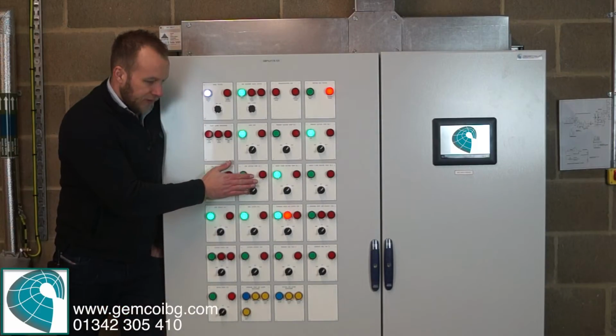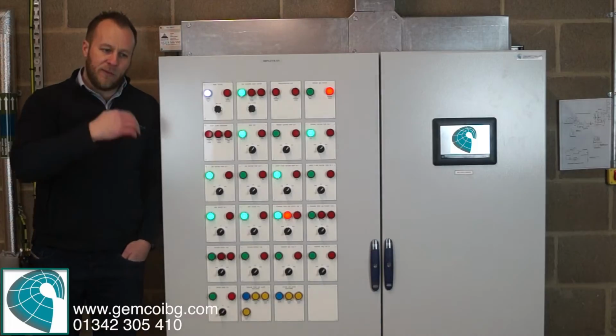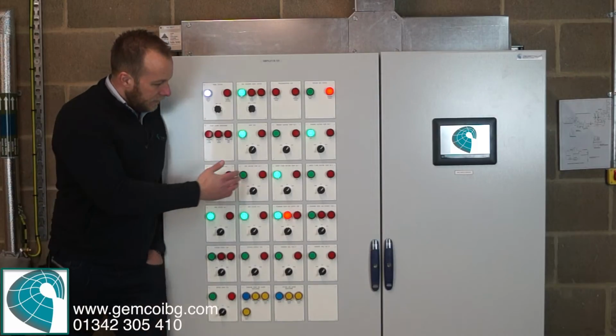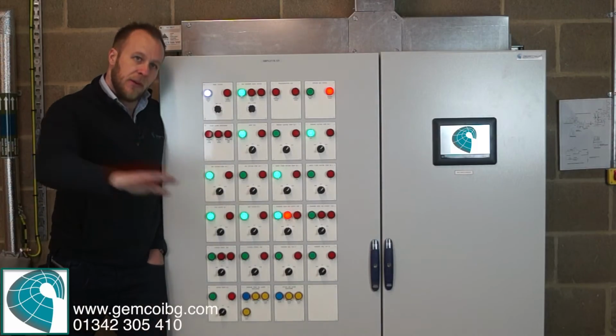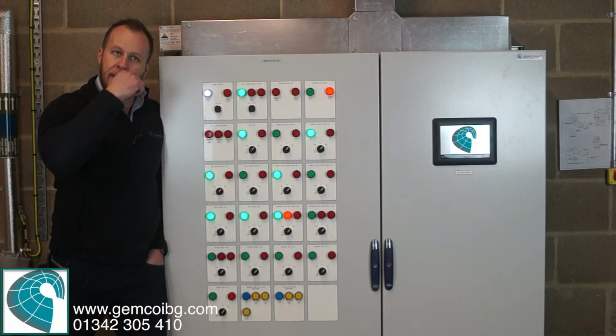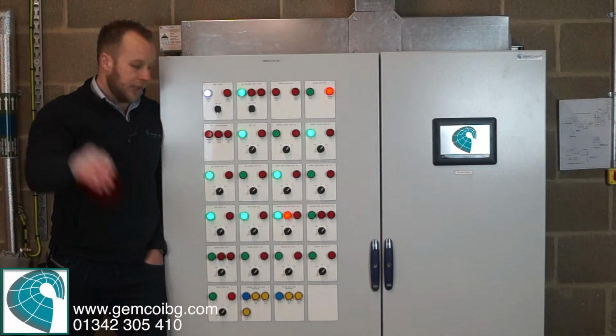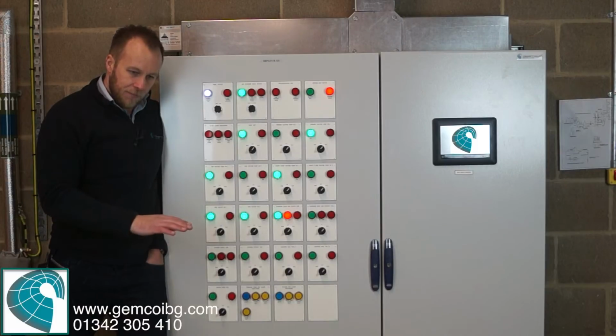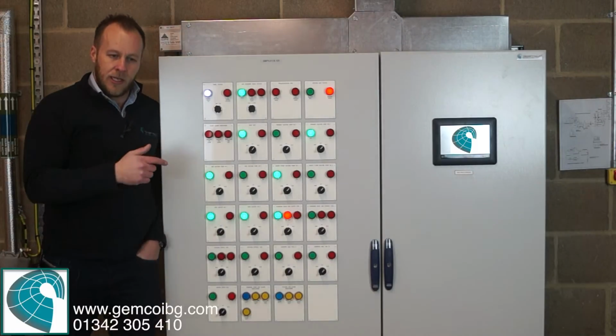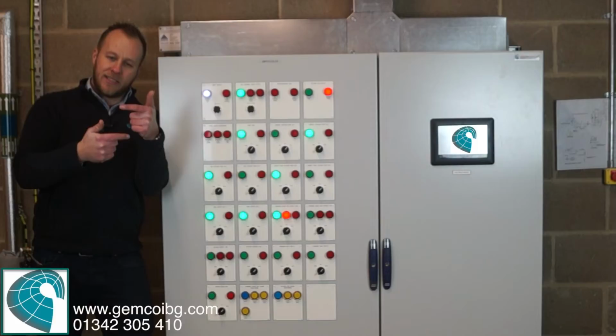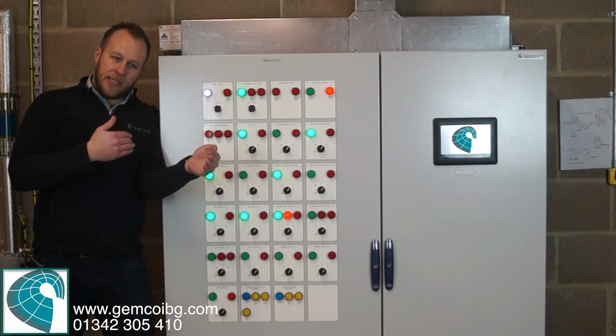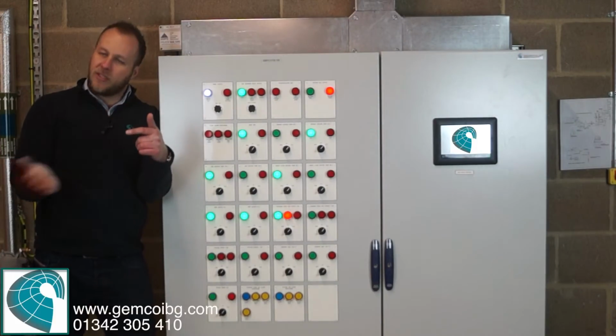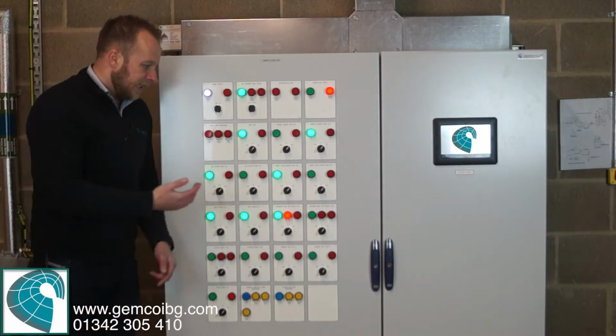The AHU pumps serve the air handling units, all the ventilation with heating valves, but it's constant temperature, so whatever's coming off of the heater out there, the boiler, will go to the air handling unit. So there's no modulation of that temperature until it gets to the air handler, and then the air handler decides, well, I need 21 degrees, so I better open my valve a bit, and it's got the temperature there to use if it needs it.